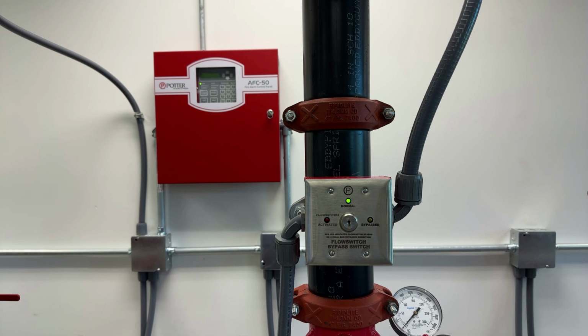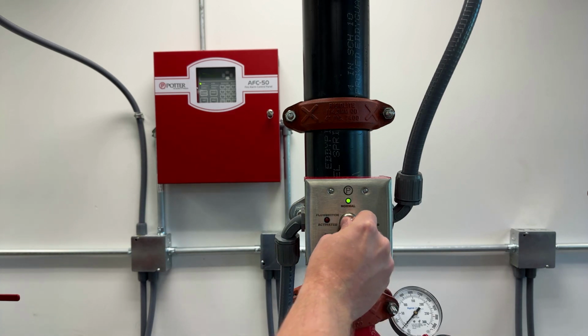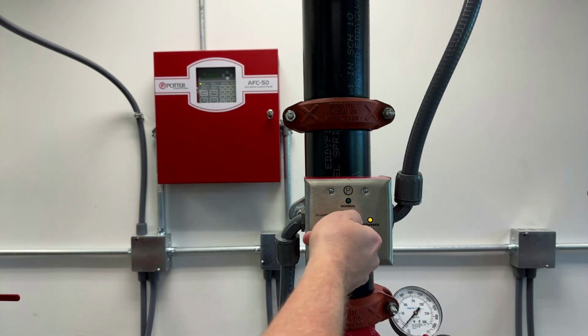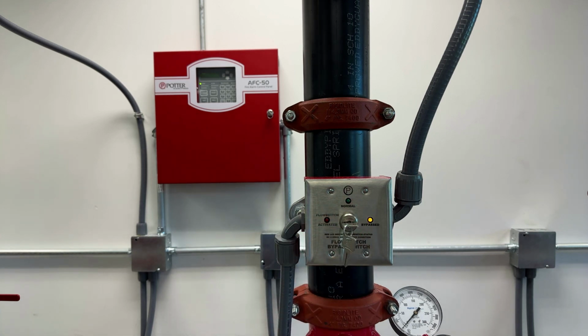To bypass the flow switch alarm, insert the key into the FSBS and turn to bypass. This will disconnect the flow switch from the fire alarm control panel and/or local alarm while simultaneously lighting an amber LED on the switch plate to indicate that the water flow alarm has been bypassed. This will also send a trouble signal to the fire alarm control panel. This condition cannot be cleared until the FSBS has been restored to normal.